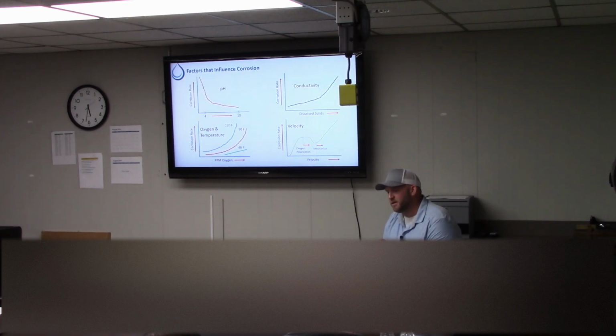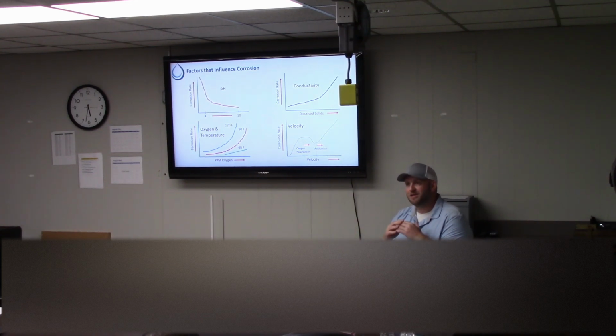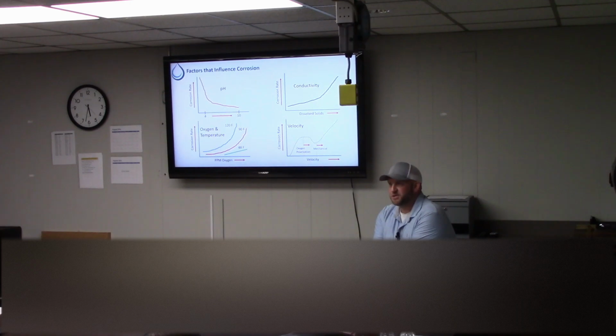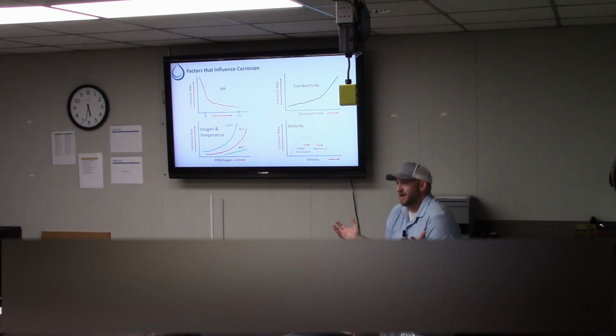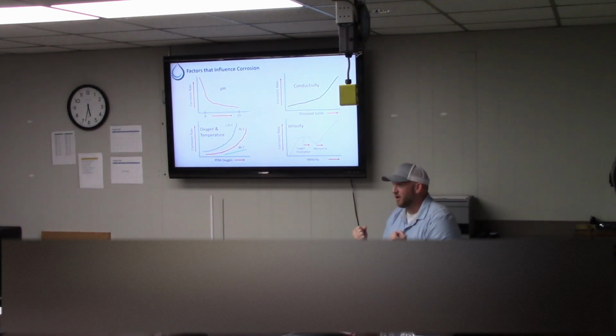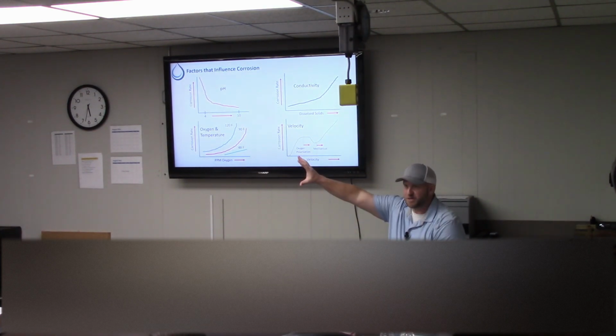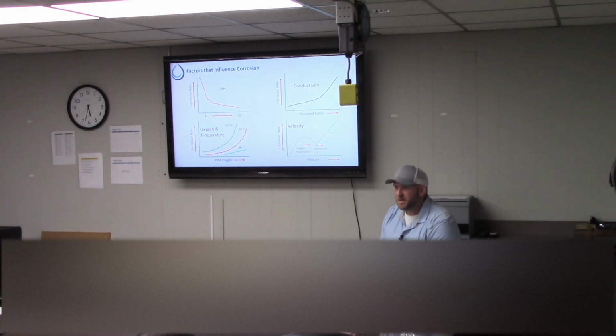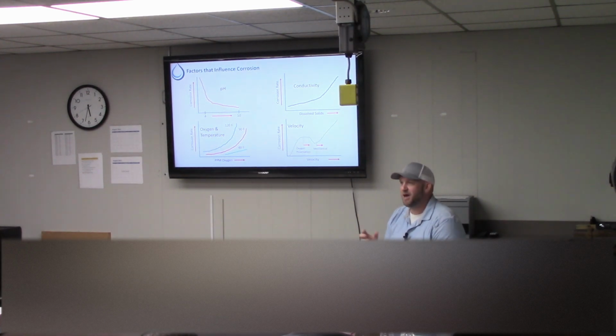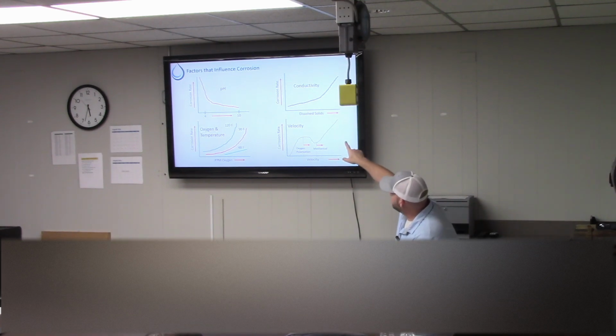It's a little more prevalent in boilers because of the temperatures, obviously. But where you have high heat exchange surface temperatures on your chiller, maybe a 110 degree skin temperature, at that point of highest heat transfer, where the water is oxygenated—and you better believe it's oxygenated because that cooling tower is a huge air scrubber, so max saturation of oxygen is already present—now you heat it up, and that oxygen is going to want to tickle that metal in a bad way. And that bad touch is going to lead to pitting. We've got some pictures, because I think pictures are worth at least 10 minutes of me talking. We'll get to that in a minute.